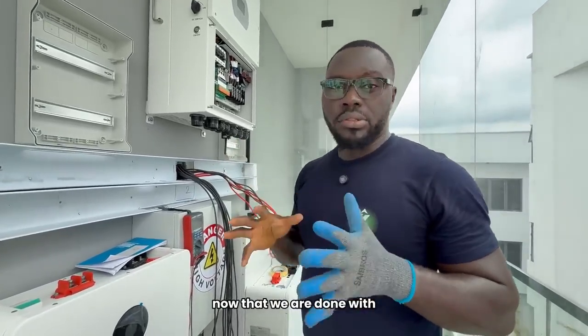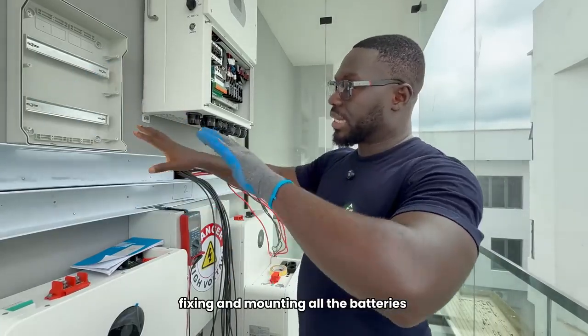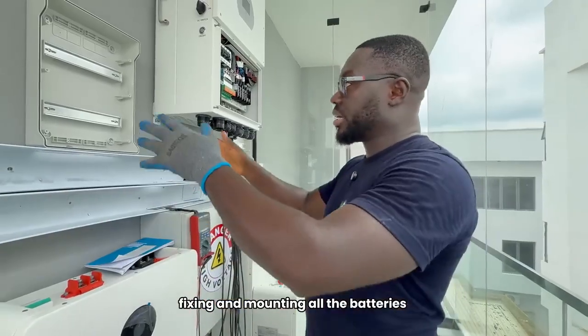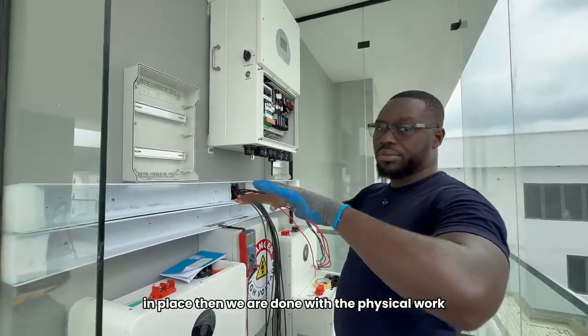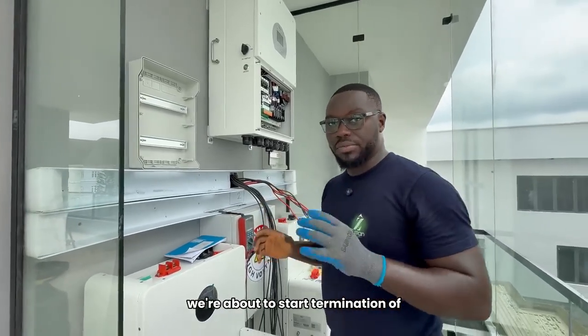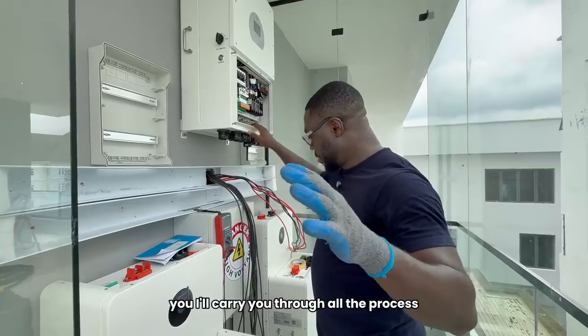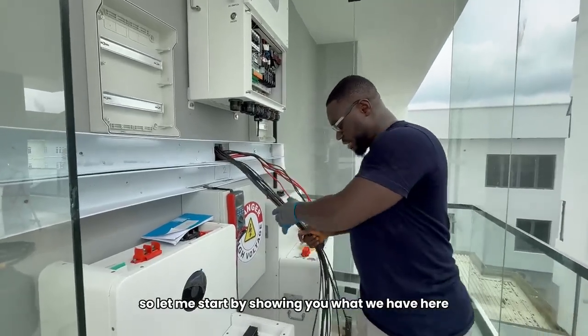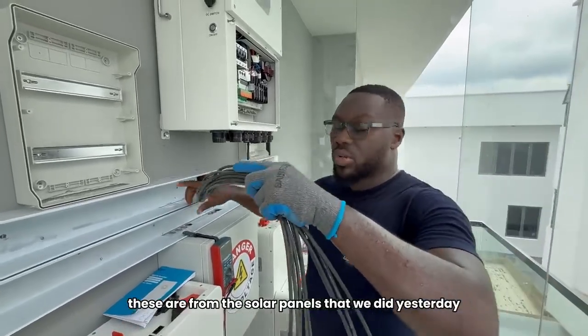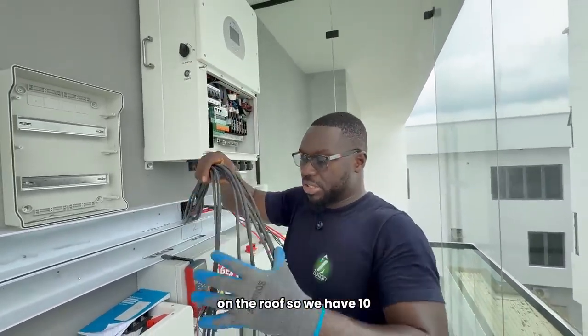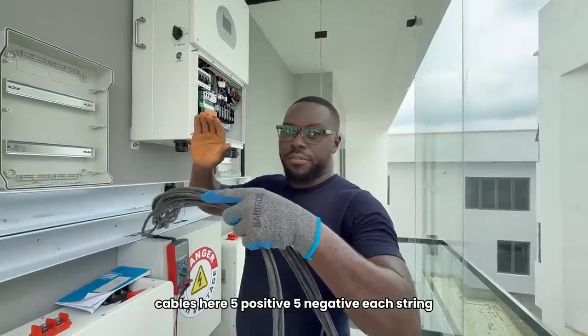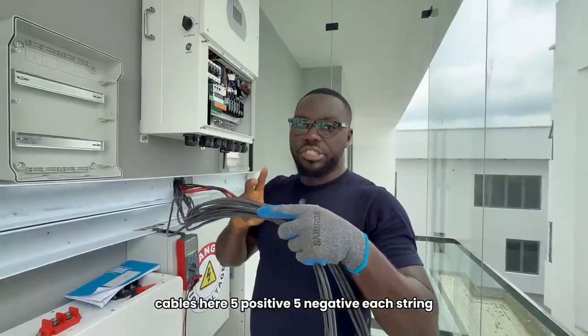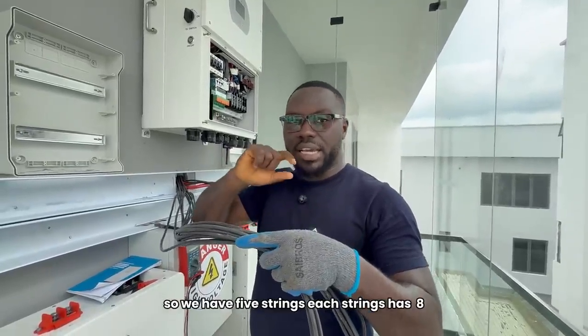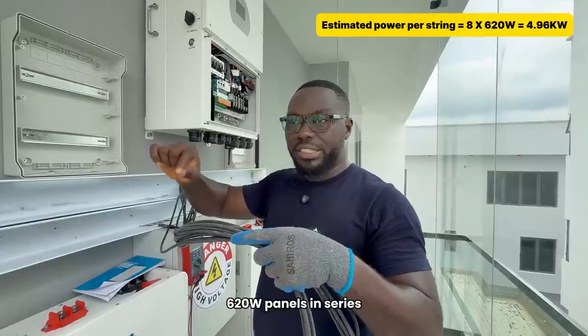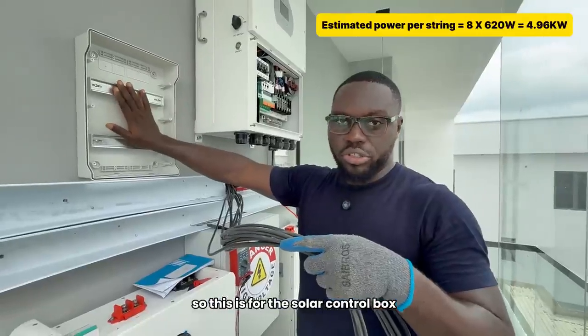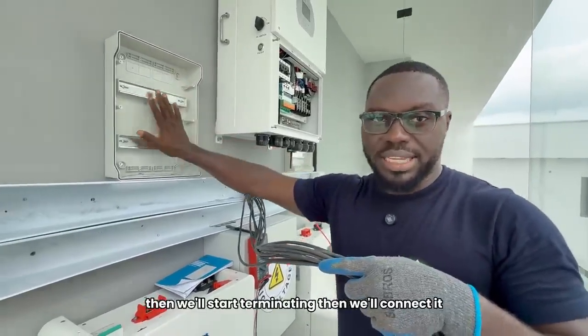Okay, so now that we are done with fixing and mounting all the batteries, the boxes, the inverter in place, then we are done with the physical work. We're about to start termination of all those, and I'll carry you through all the process. So let us start by showing you what we have here. These are from the solar panels that we did yesterday on the roof. So we have 10 cables here, 5 positive, 5 negative, each string. So we have 5 strings. Each string has 8 620-watt panels in series. So this is for the solar control box. So we'll start populating it, then we'll start terminating, then we'll connect it.